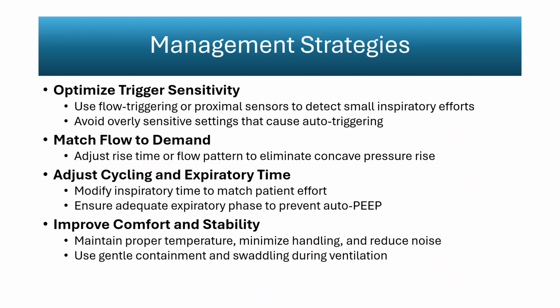Next, flow must match the infant's inspiratory demand. If flow delivery is slower than the infant's natural effort, the pressure waveform develops a concave scooped appearance as the infant pulls harder to achieve the desired volume. Adjusting the rise time or modifying the flow pattern restores synchrony by ensuring the ventilator provides adequate flow at the beginning of inspiration.